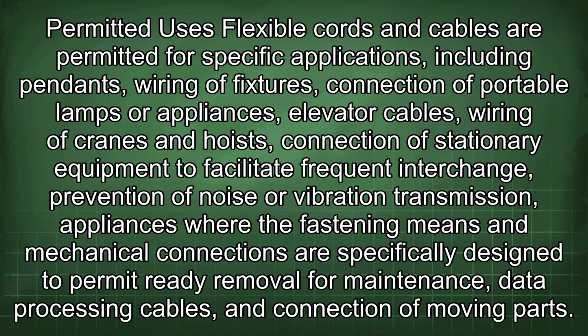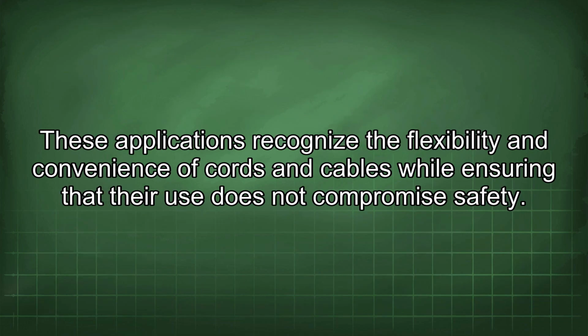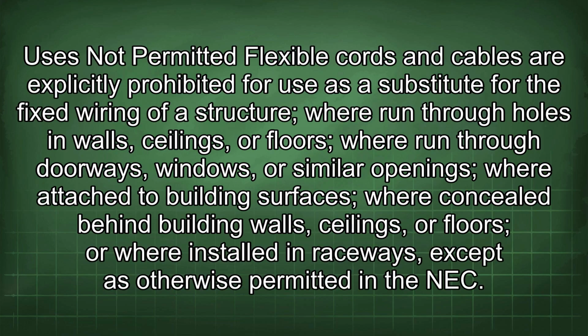or vibration transmission. Appliances where the fastening means and mechanical connections are specifically designed to permit ready removal for maintenance, data processing cables, and connection of moving parts. These applications recognize the flexibility and convenience of cords and cables while ensuring that their use does not compromise safety.